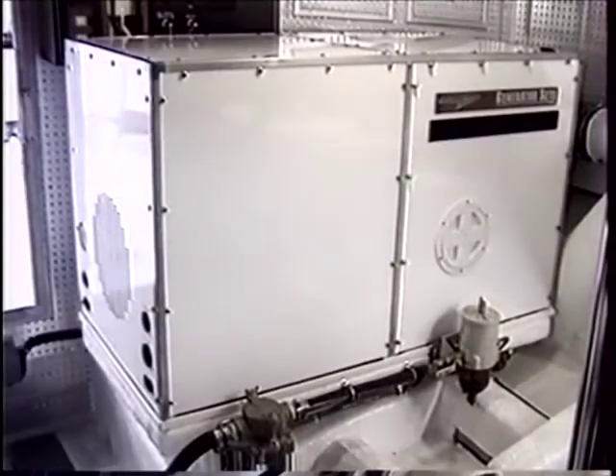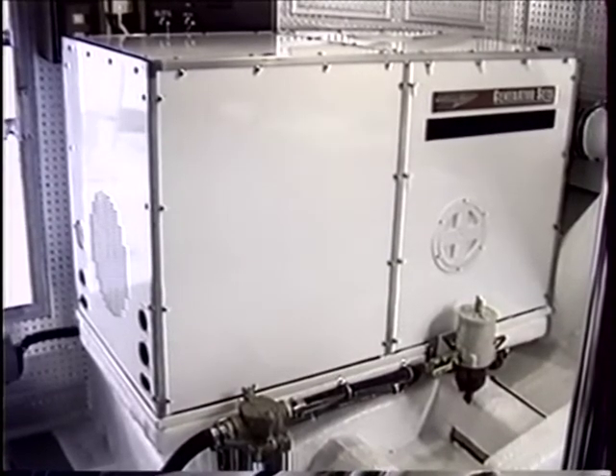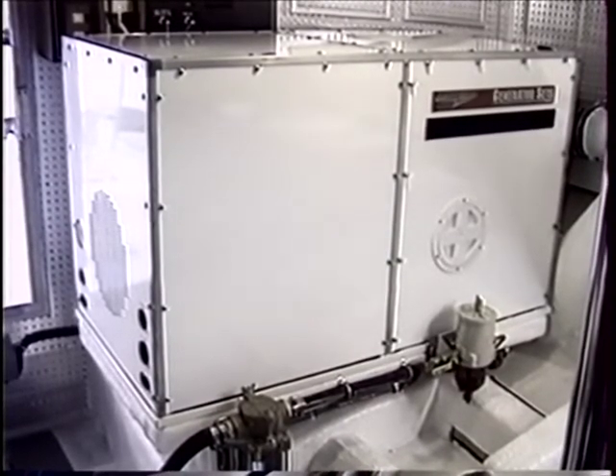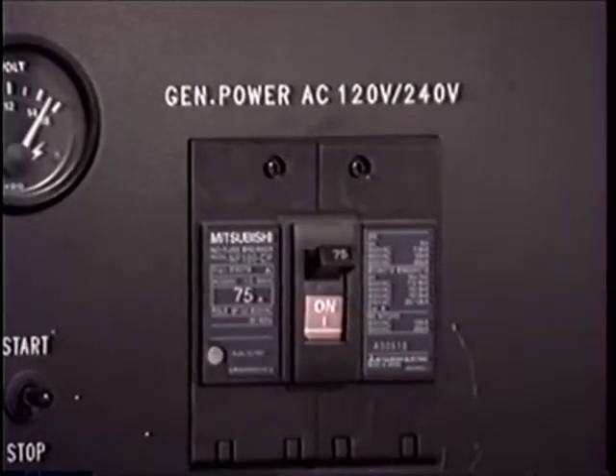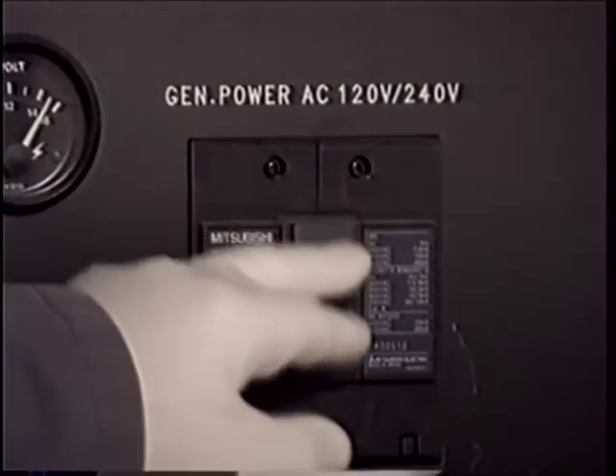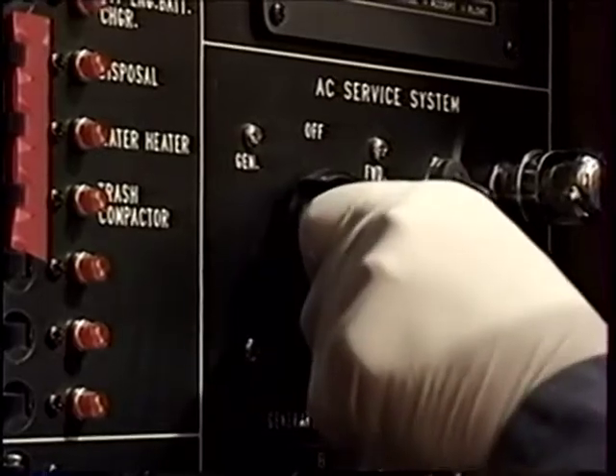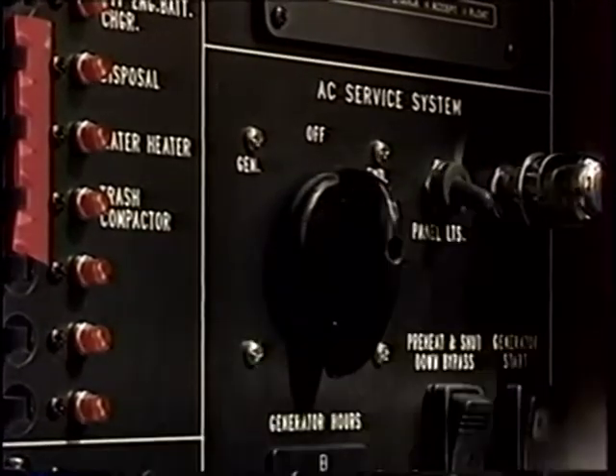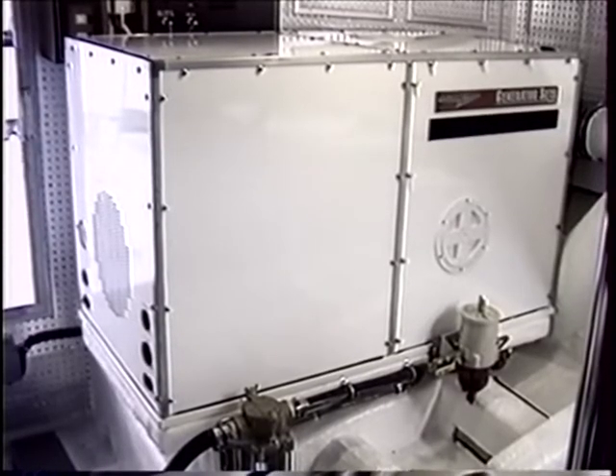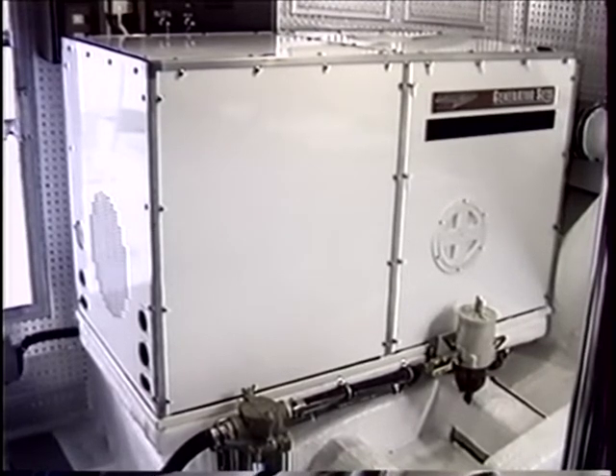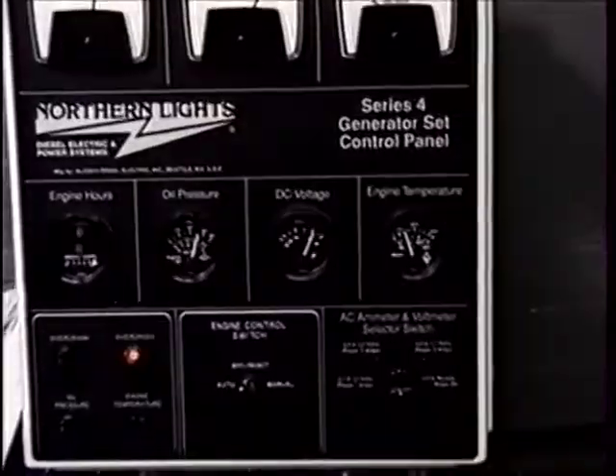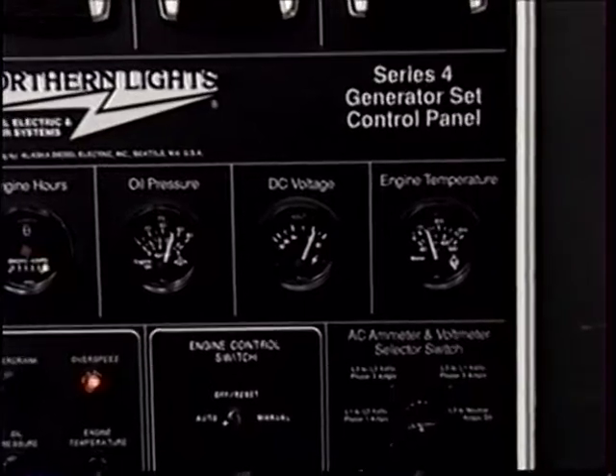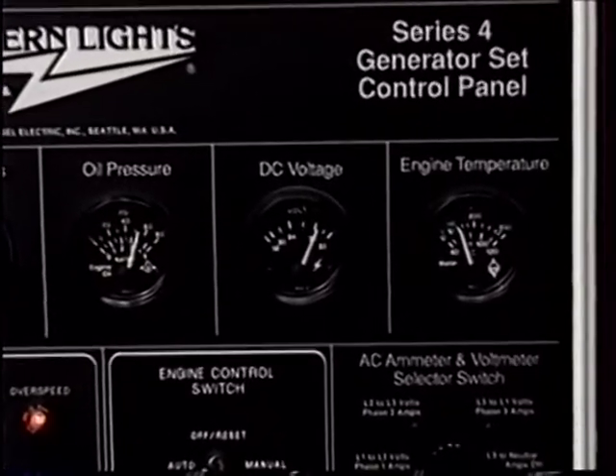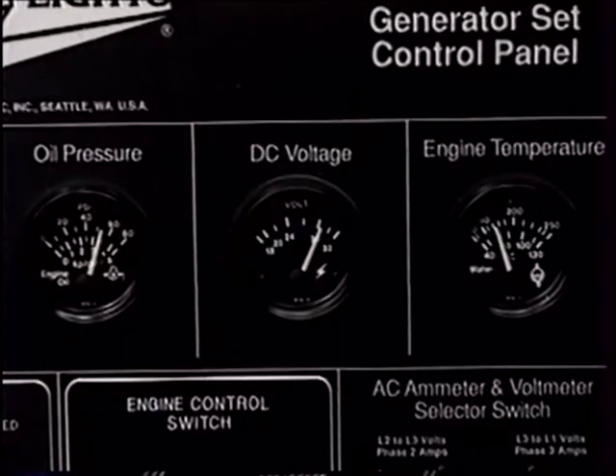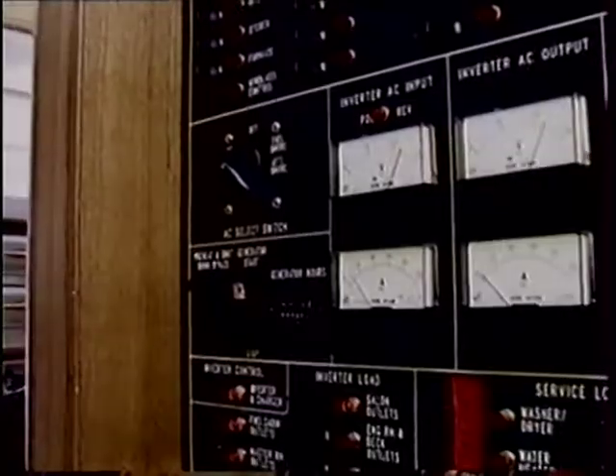There are several steps to follow when you are ready to shut down your Northern Lights generator set. First, remove the load being applied to the unit by operating the main circuit breaker or utilizing the load selector switch. Allow the unit to run for a few minutes without load to stabilize and cool down. Observe the engine temperature and engine oil pressure gauges to see that they are in the normal range. You can now shut down the unit.